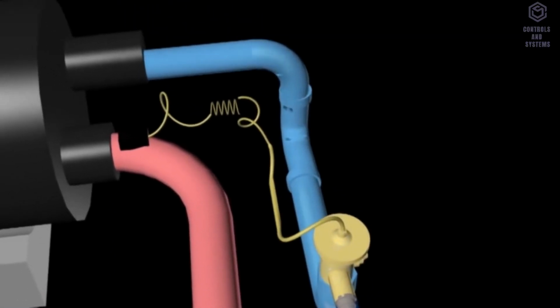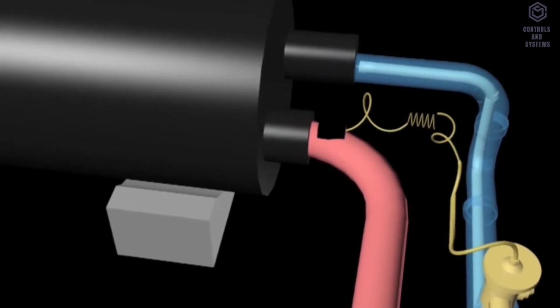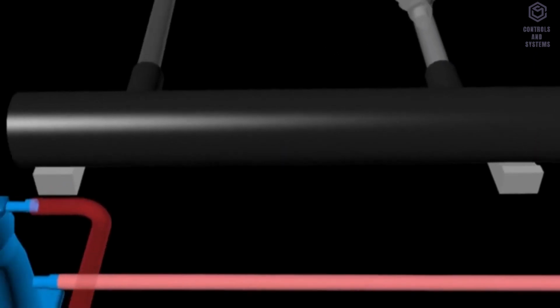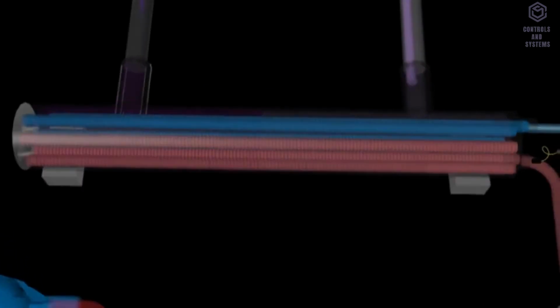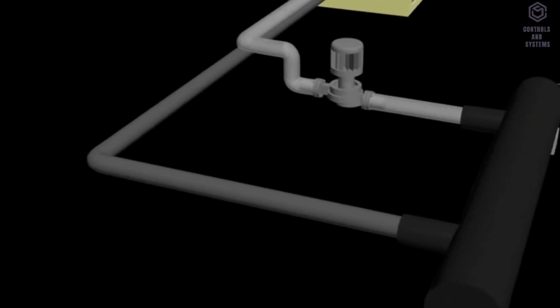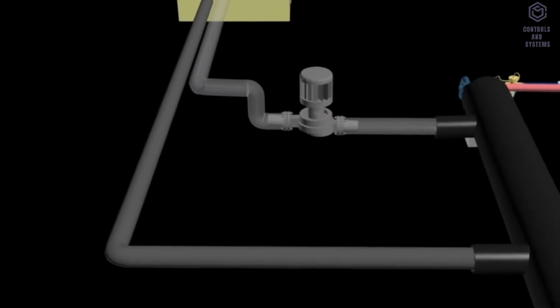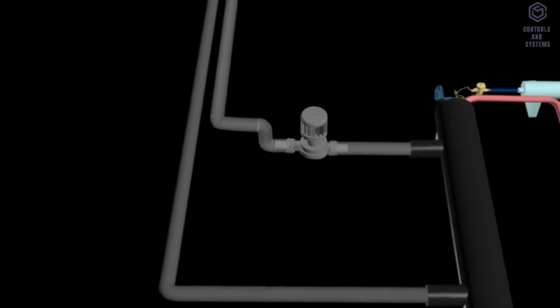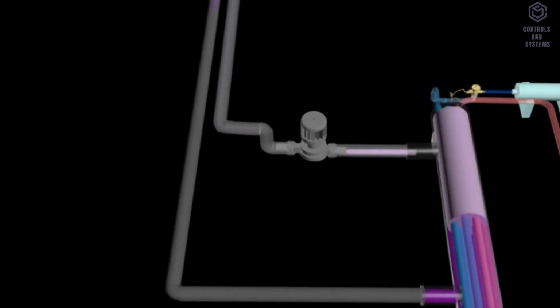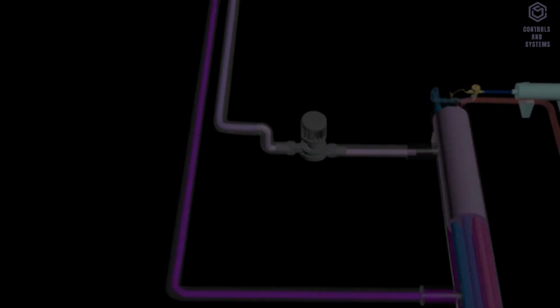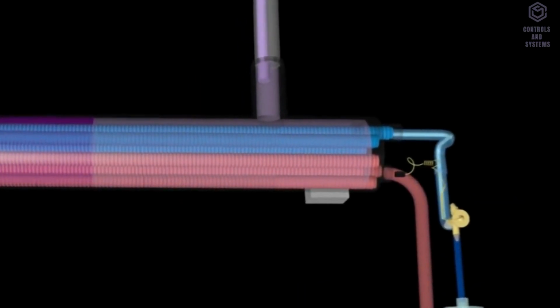Evaporator. The refrigerant as low pressure liquid coming out from the expansion valve will flow into the evaporator at low temperature. In the evaporator, the heat from the chilled water which comes out from the air handling unit will be absorbed by the refrigerant due to the temperature difference. When the liquid refrigerant at low temperature and pressure absorbs heat from the chilled water, the refrigerant will evaporate into low pressure gas.